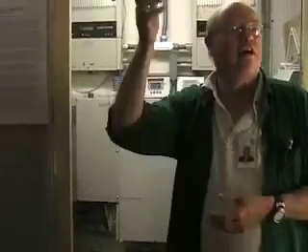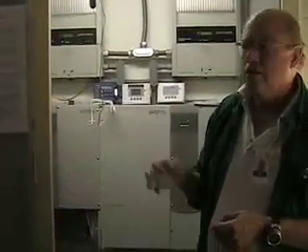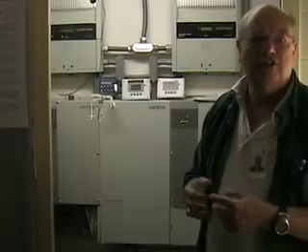One of them heats up the hot water, which you see the tubes here in the floor. That provides our heating for the house. As you know, radiant floor heating is the best that there is, most uniform, and it doesn't dry out the air because it's just coming up through the floor, not with hot air and other systems. We also have our domestic hot water running through that tank at 115 degrees, in a separate coil.